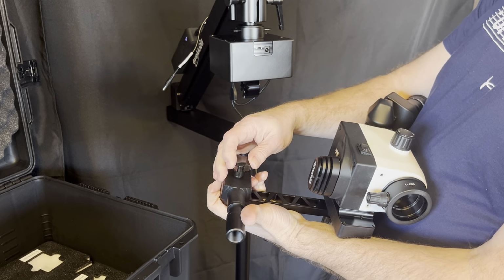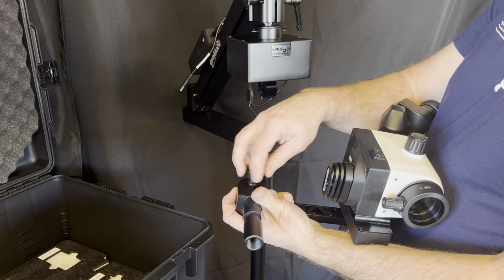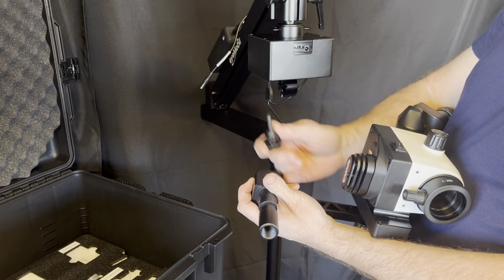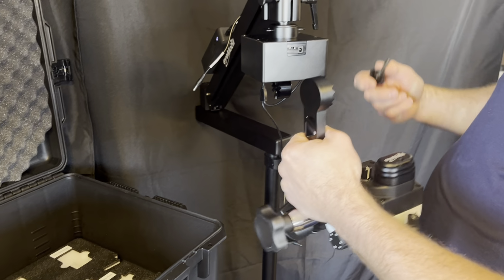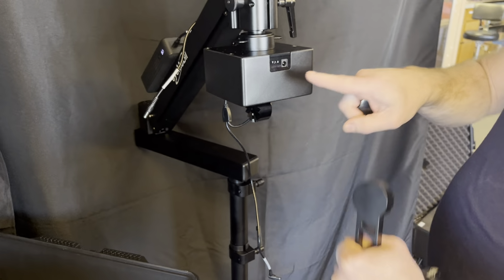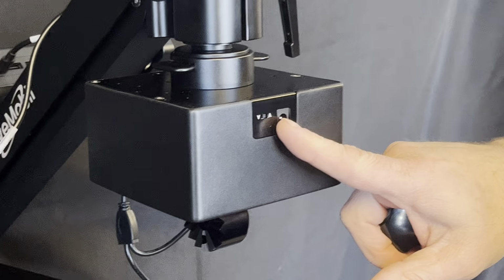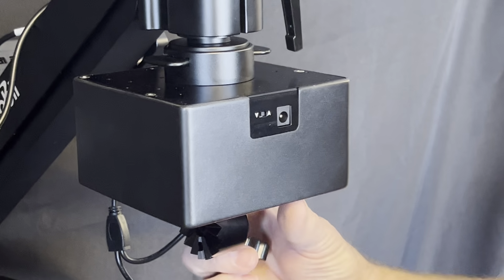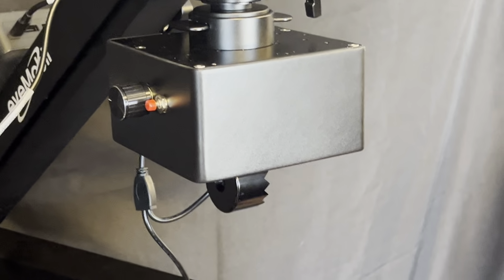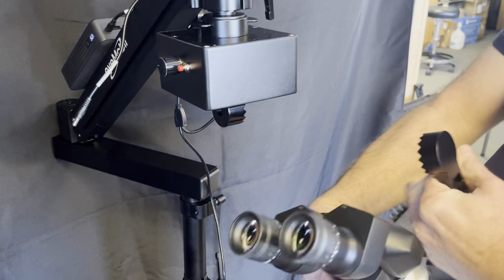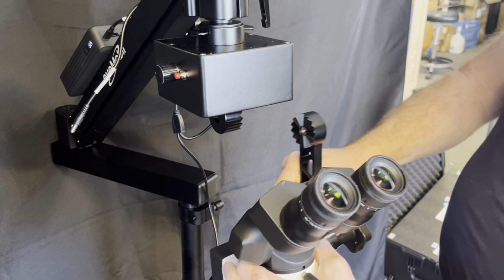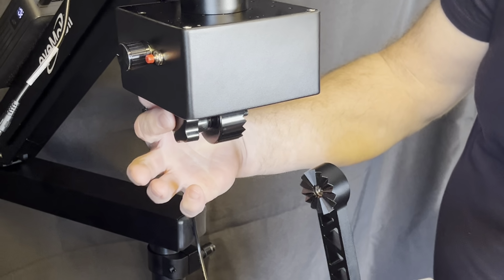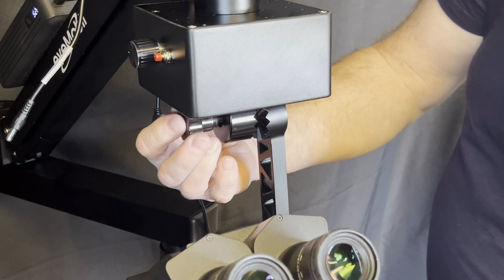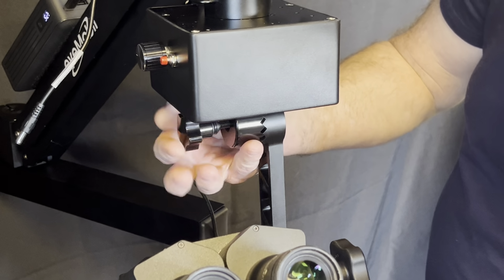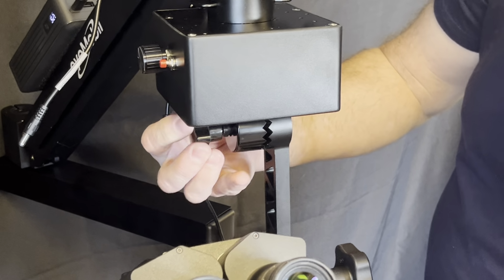Now we'll remove the standard rosette post from the microscope by turning this star-shaped thumb knob. This screw will be used to connect the head of the scope to the XY unit. When in the hang down configuration, the battery connection on the XY unit should be rotated to the rear. That makes the orientation of the rosette correct for putting the microscope on. We'll insert the thumb screw and begin to attach the rosette arm of the microscope head to the XY unit.